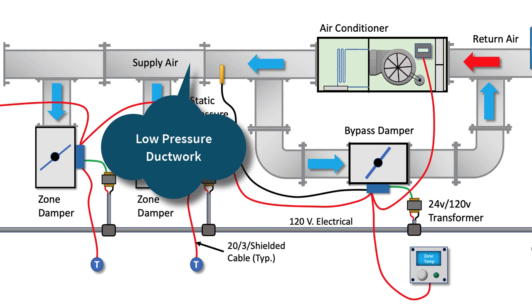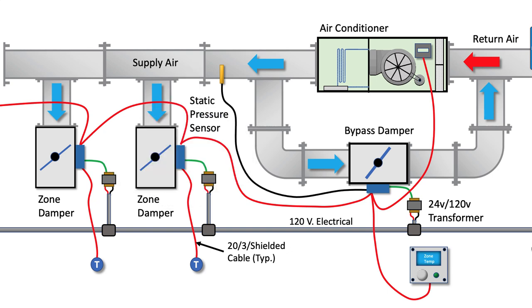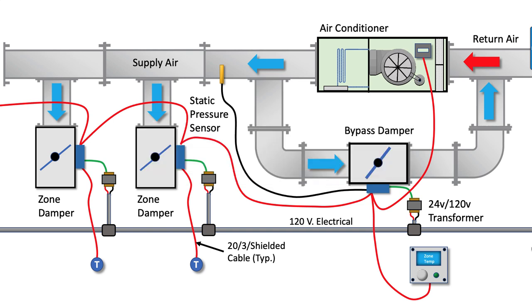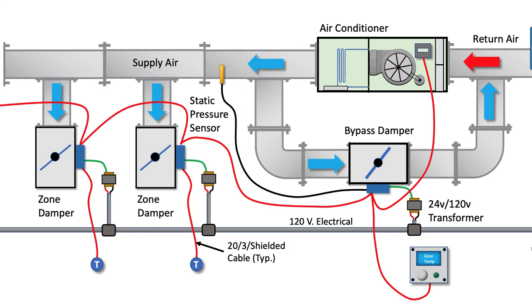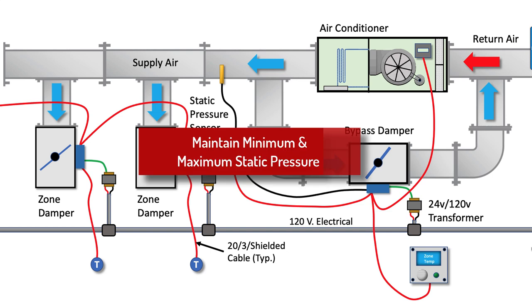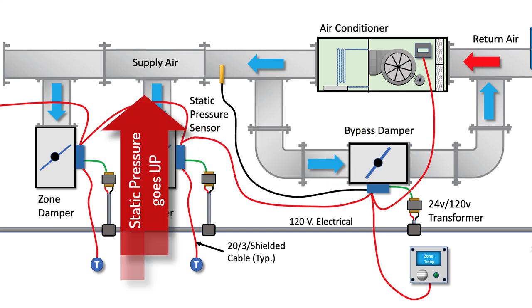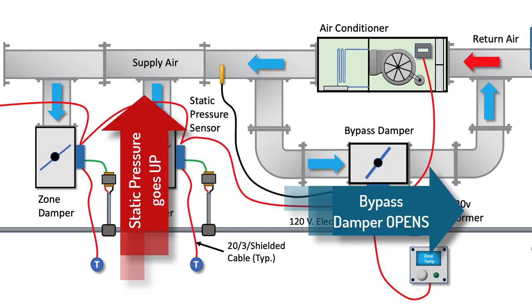The bypass damper also allows the ductwork to be installed using low-pressure duct, as the bypass damper prevents buildup of static pressure in the ductwork. Excessive static pressure could cause the joints or seams of the duct to come apart, creating leaks. The bypass controller uses a duct static pressure sensor installed in the supply air ductwork. The controller is set by the user to maintain a minimum and maximum pressure in the supply duct main, and as static pressure increases due to zone dampers closing, the sensor modulates the bypass damper to route the excess air.